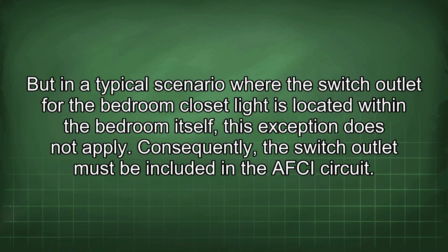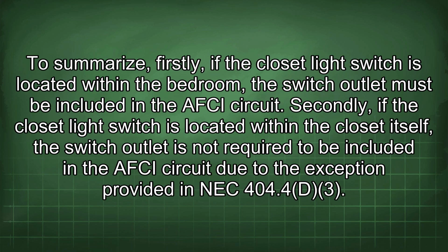But in a typical scenario where the switch outlet for the bedroom closet light is located within the bedroom itself, this exception does not apply. Consequently, the switch outlet must be included in the AFCI circuit. To summarize, firstly, if the closet light switch is located within the bedroom, the switch outlet must be included in the AFCI circuit. Secondly, if the closet light switch is located within the closet itself, the switch outlet is not required to be included in the AFCI circuit due to the exception provided in NEC 404.4D3.